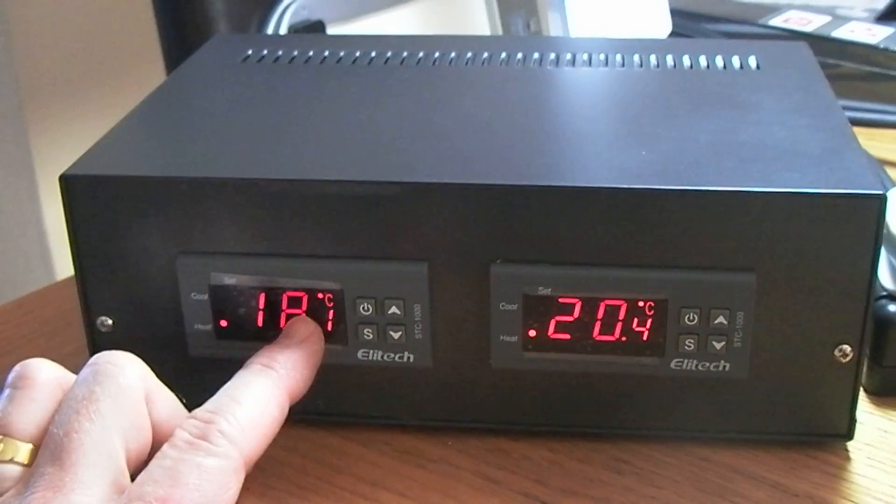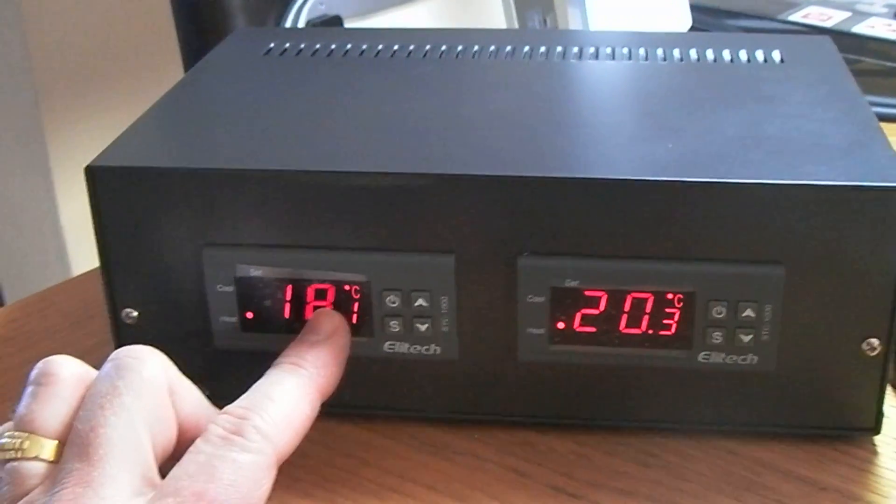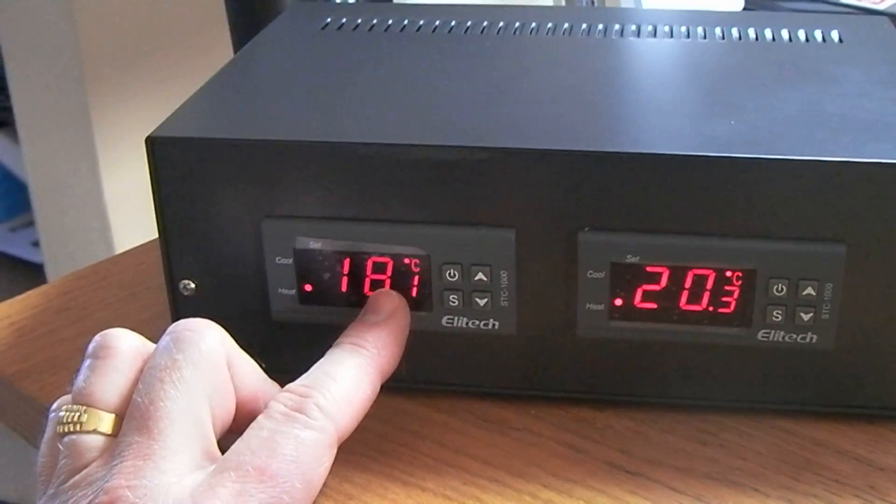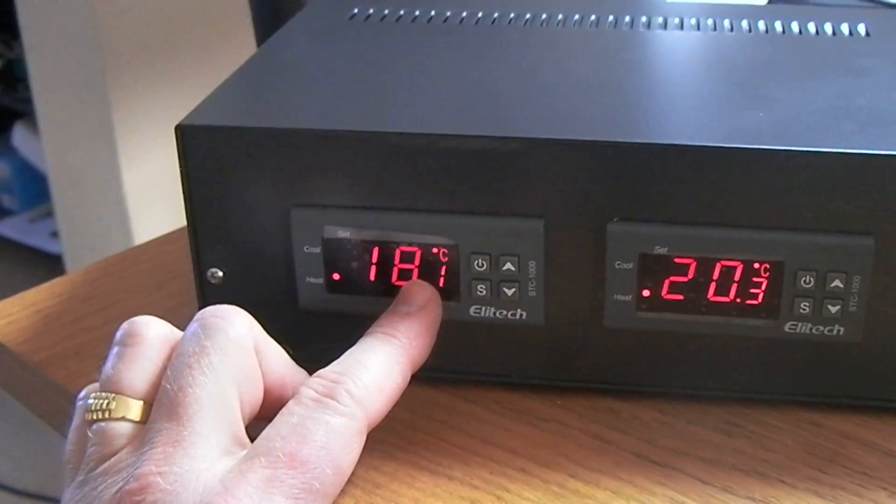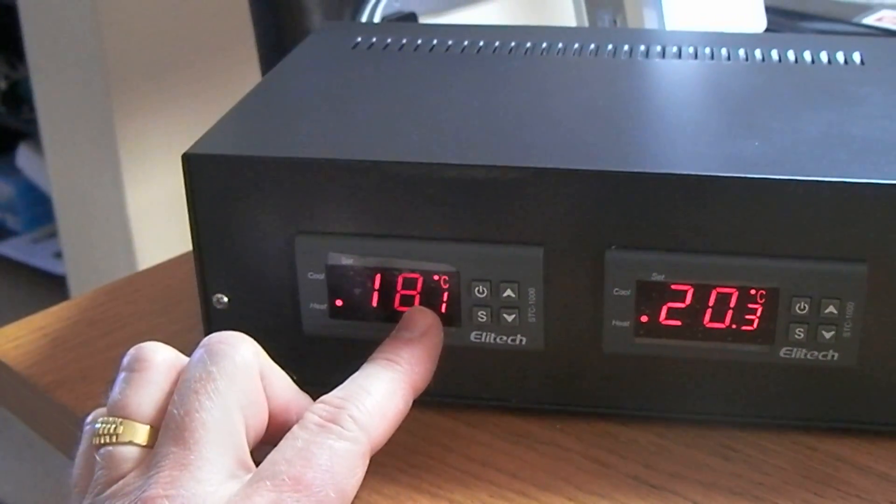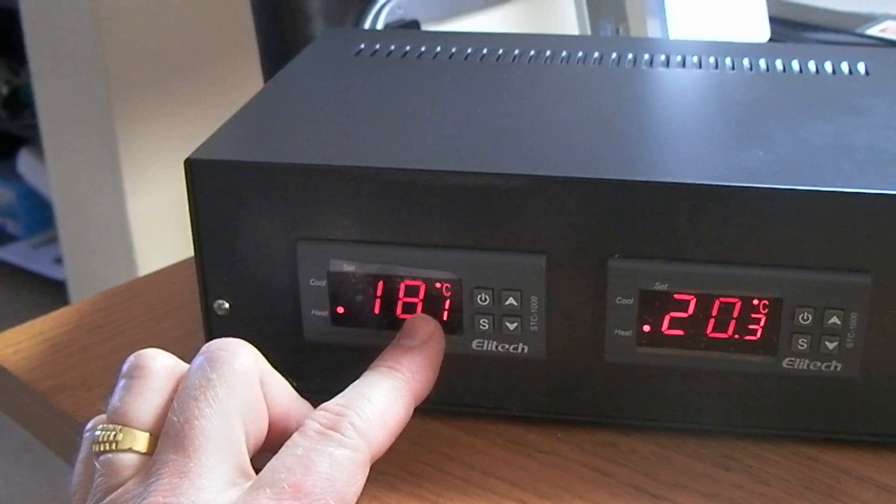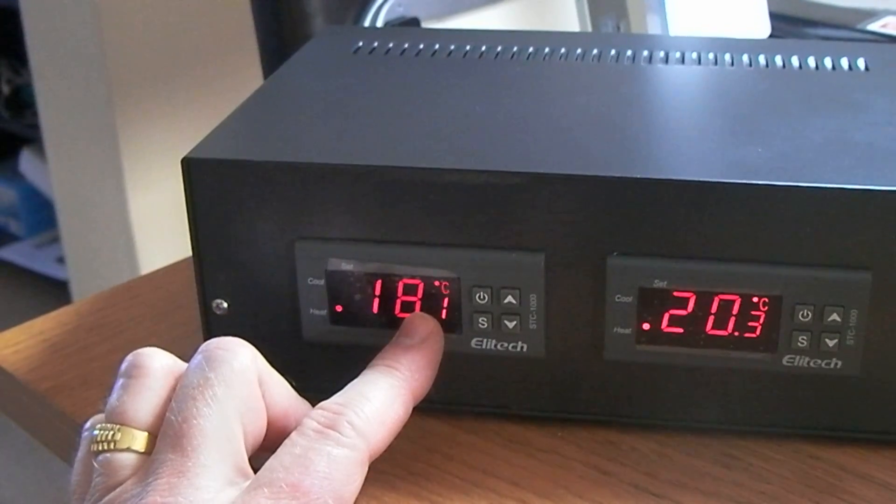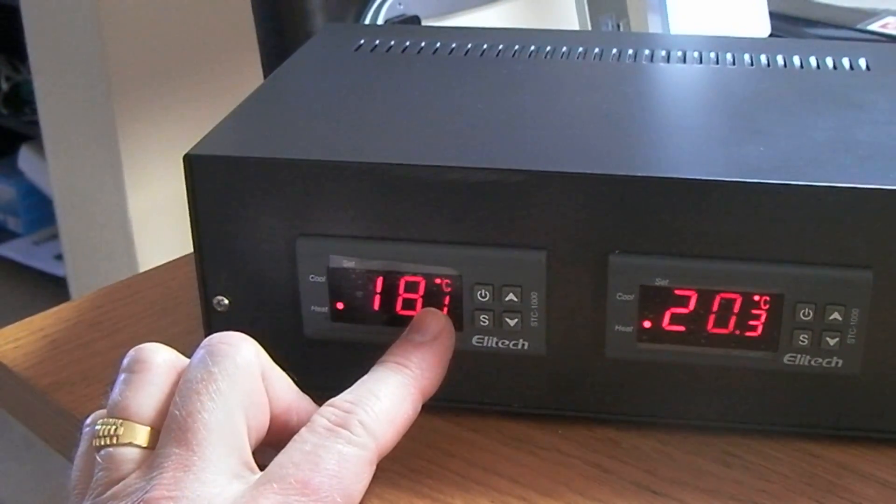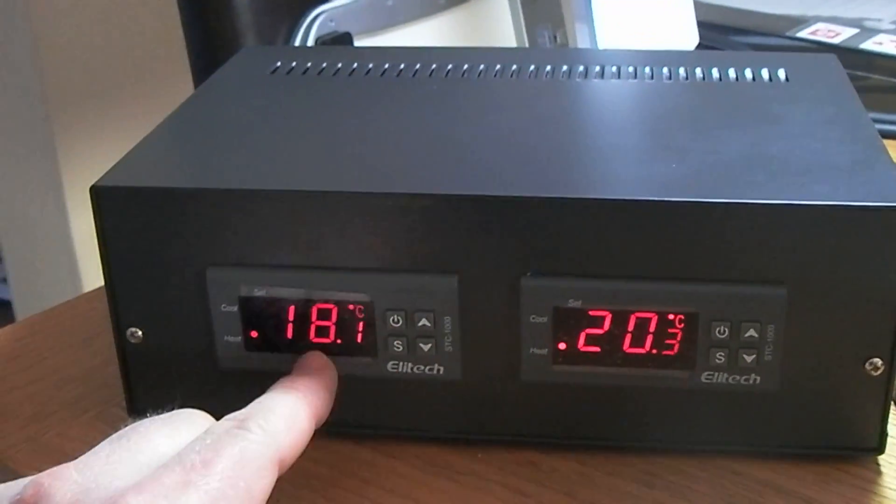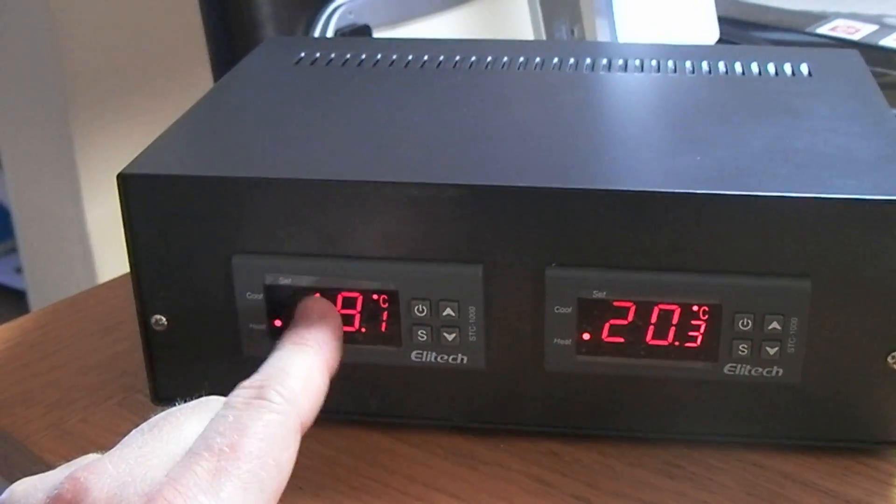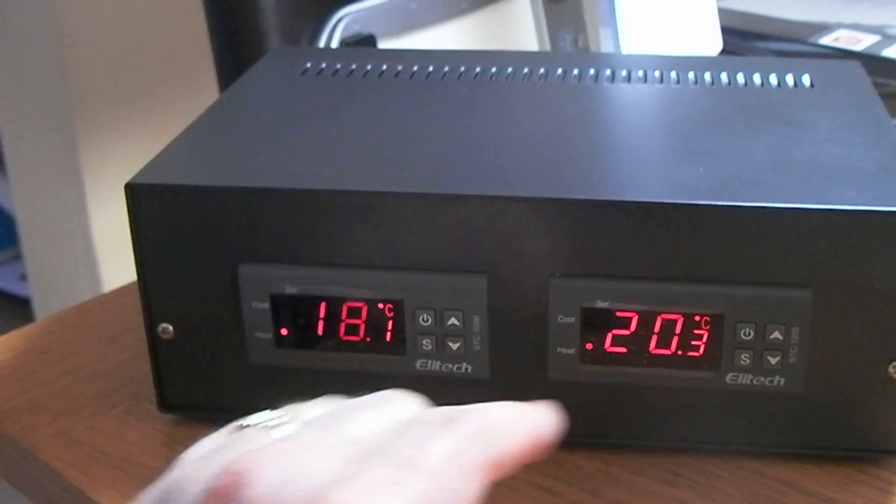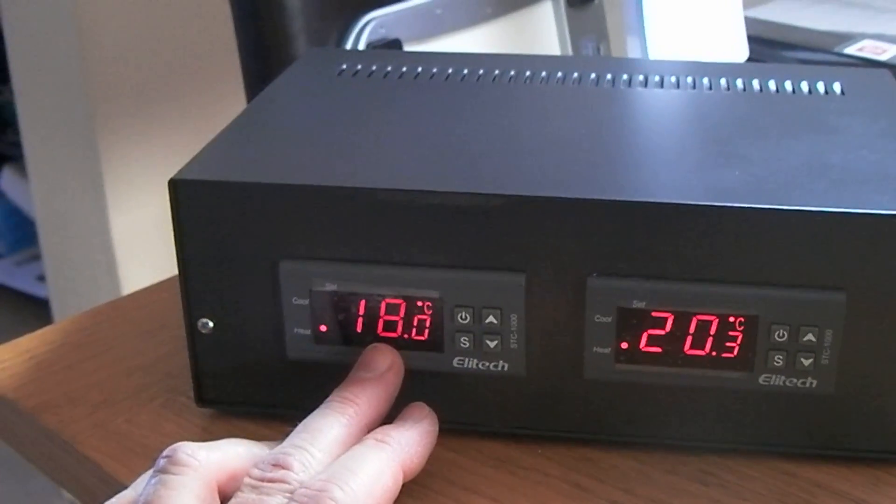And then this one that has been set two degrees lower than the normal tank temperature will then kick in, and the heater will start to heat. So again, we've got redundancy built in and over-temperature protection on both of the heaters.